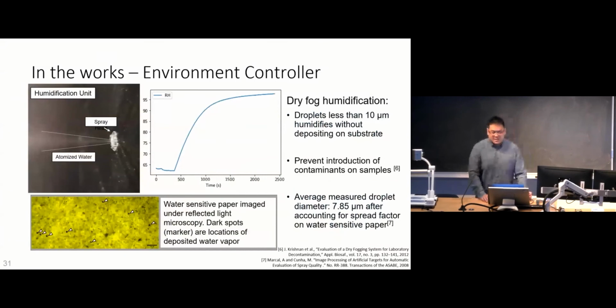In addition to regulating the substrate temperature, the ability to control the relative humidity within the instrument is also of interest. For example, in maintaining dew point to prevent evaporation of the materials dispensed, such as the cell solution, or perhaps lysis buffer, which may be preloaded into the chips. However, humidification with small droplets is desirable in order to prevent the deposition of external genomic material onto the nanowell sample. Therefore, we use dry fog humidification using a modified airbrush.